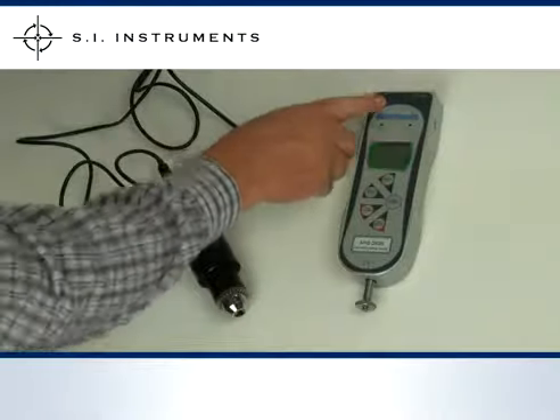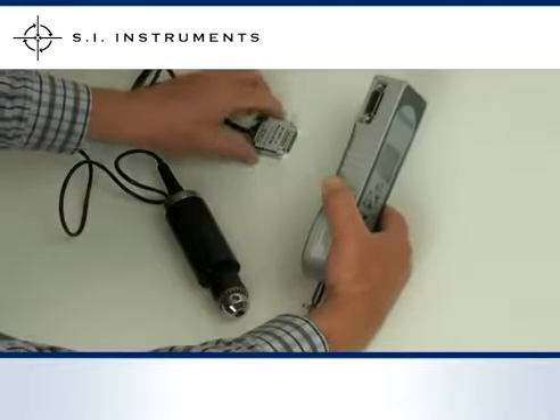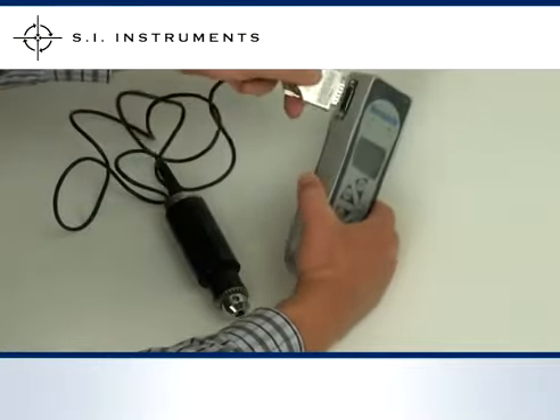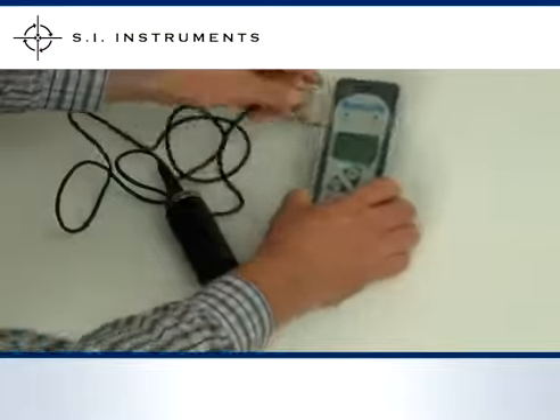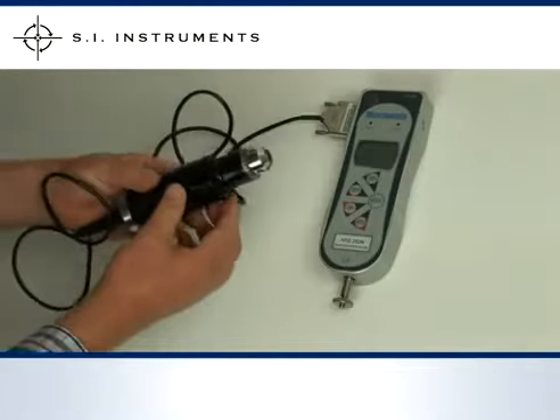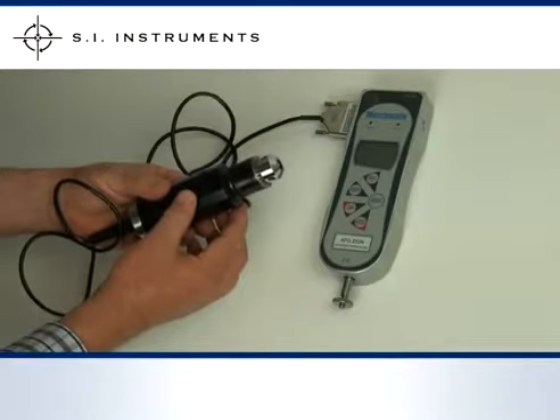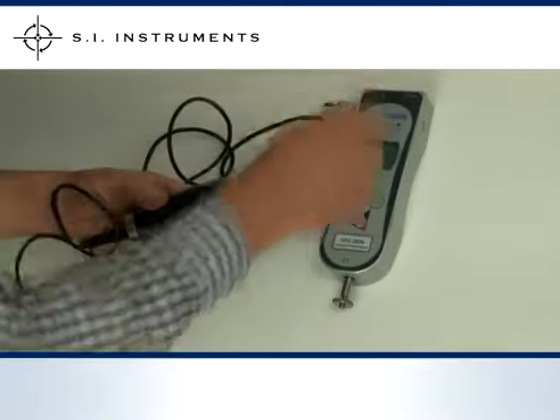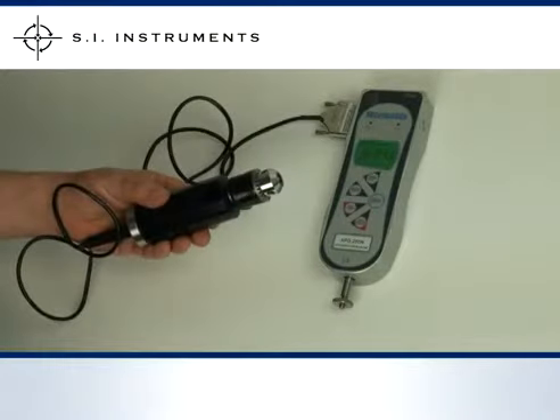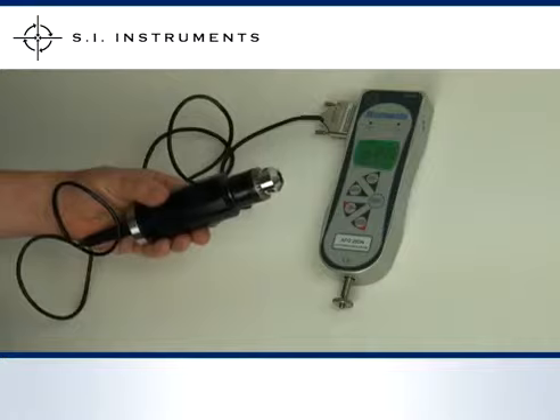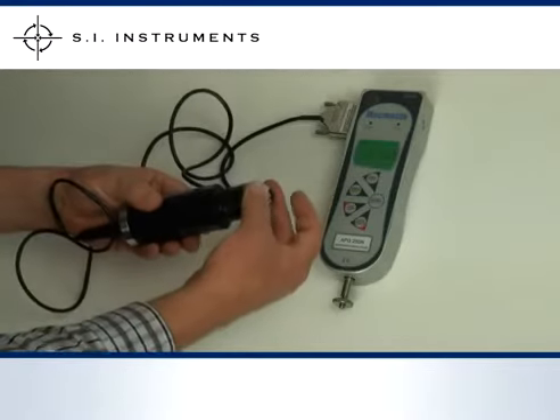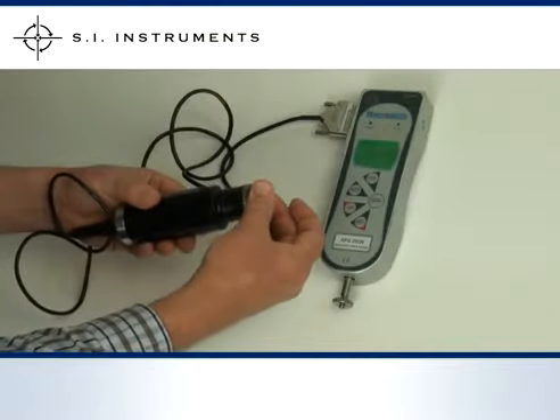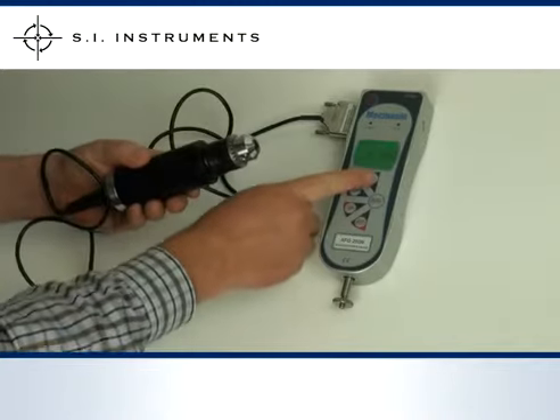Here we have a Mecmesin torque screwdriver 10 Nm. All we need to do is connect the torque screwdriver to the input connector and turn the gauge on. The gauge will recognize the transducer and its capacity during startup and adopt the correct calibration settings. There is no need for telling the electronics what is connected, with the unit now immediately ready for action.